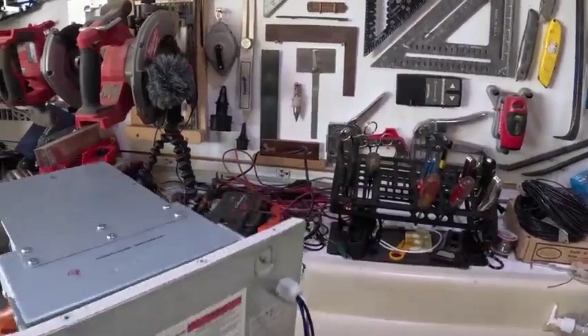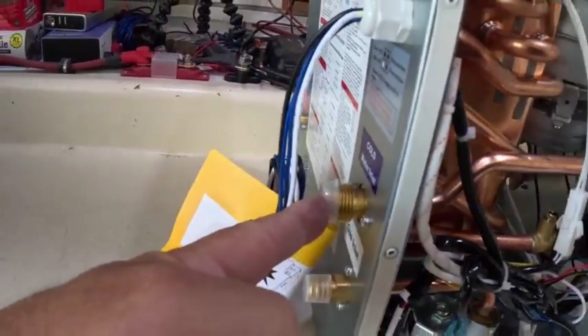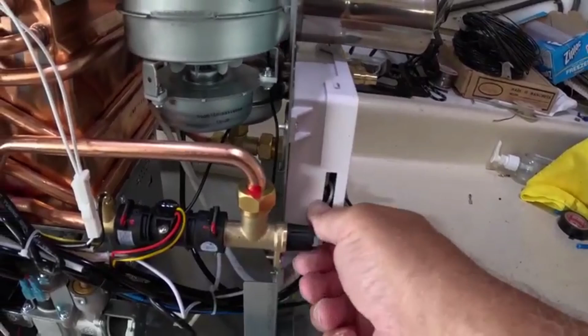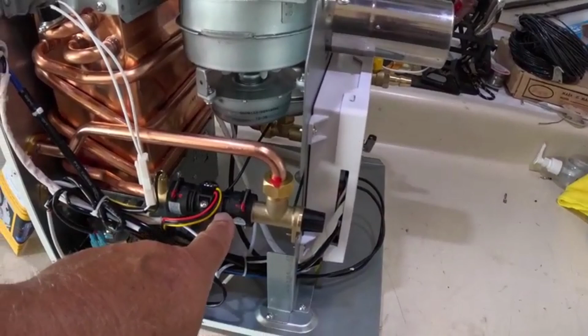So let's take a look at the way the water comes in. We have our cold water inlet here. The water comes in through this little removable filter, which you can take out and clean or possibly replace. The water goes through this flow meter, basically a set of propellers that spin. When the water flow reaches a certain level, it signals for a couple of things to happen: first the exhaust fan comes on, then the burner ignites, and then we start to get hot water.